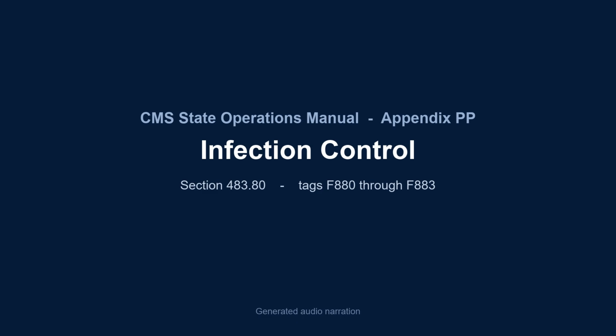Intermediate-level disinfection is traditionally defined as destruction of all vegetative bacteria, including tubercle bacilli, lipid and some non-lipid viruses, and fungi, but not bacterial spores. EPA-registered hospital disinfectants with a tuberculocidal claim are intermediate-level disinfectants. Given the broader spectrum of activity, intermediate-level disinfection should be considered for non-critical equipment that is visibly contaminated with blood. However, a low-level disinfectant with a label claim against HBV and HIV could also be used.